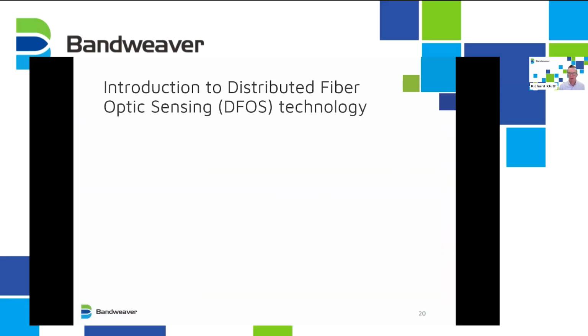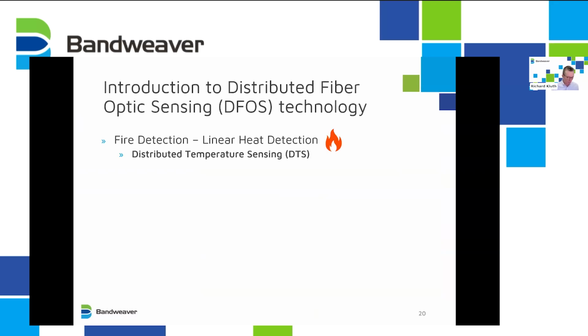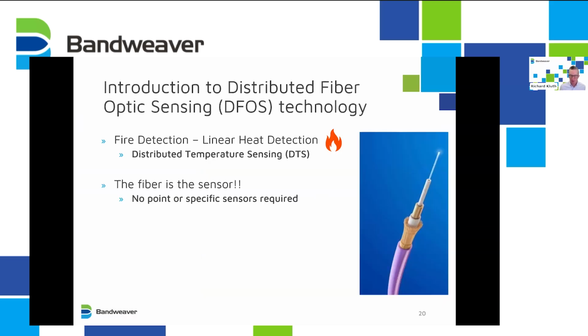So how does distributed fiber optic sensing work? Well, linear heat detection uses a technology called distributed temperature sensing, which means it measures temperature at all points. And the fiber is the sensor. There's no points or specific sensors required. The controller, the panel that you plug the cable into, makes the fiber optic sensitive to temperature, which I'll explain more on the next slide.